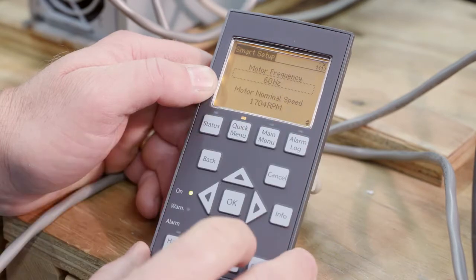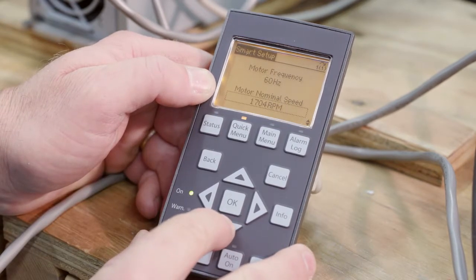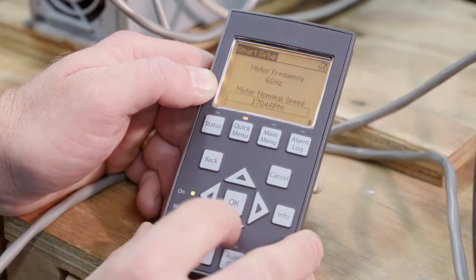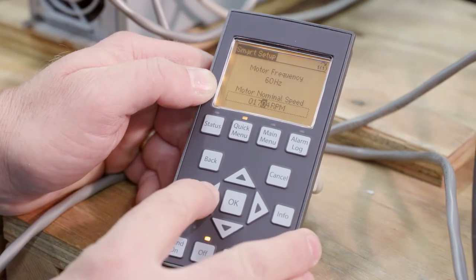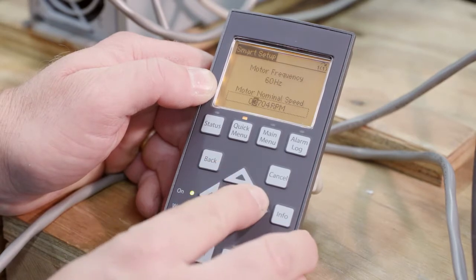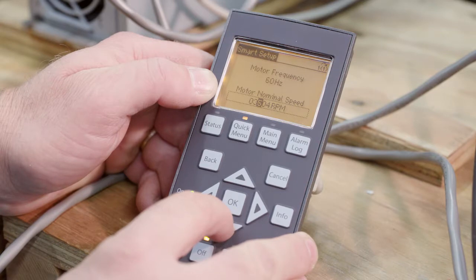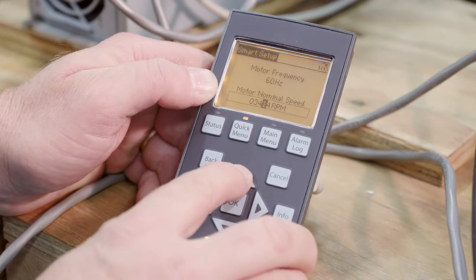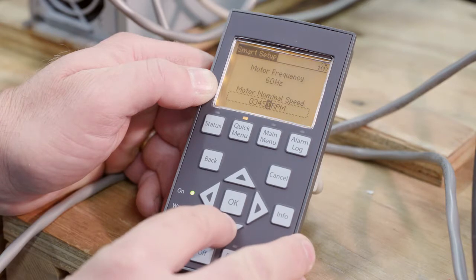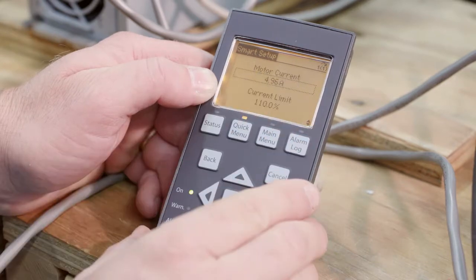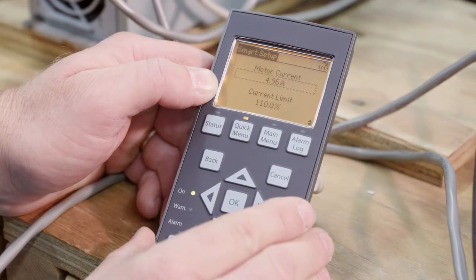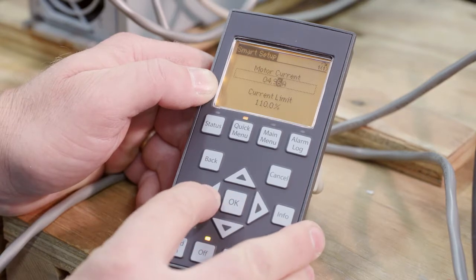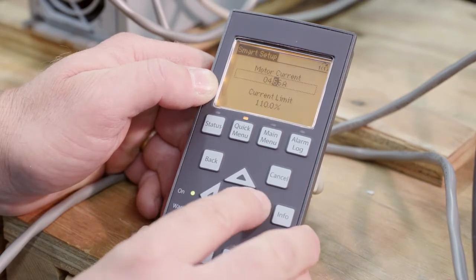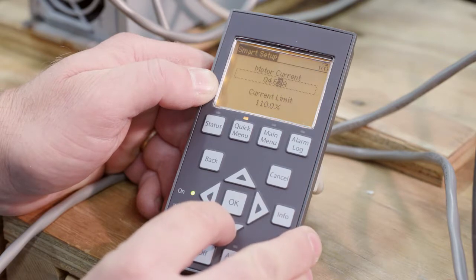Now I'm at motor frequency, which is okay. Motor nominal speed, I need to change that to 3450. So I'm going to hit the OK button and start changing this. You just move over to your position. So 3450, hit the OK and down arrow. Motor current, again, I've got to look at the motor nameplate for this information, and it's 4.6. So I'm going to change that to 4.6. Okay, down arrow.